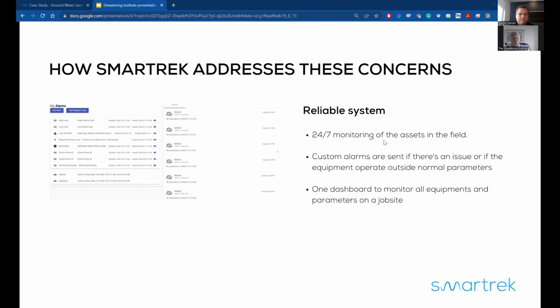Basically, this alarm system works with multiple groups. You can have an 8-to-5 group, an after-hours group, a weekend group, and also a critical group for when nobody answers. The system starts by contacting the primary group during normal hours, then if nobody answers, it switches from one group to another until someone acknowledges the error.